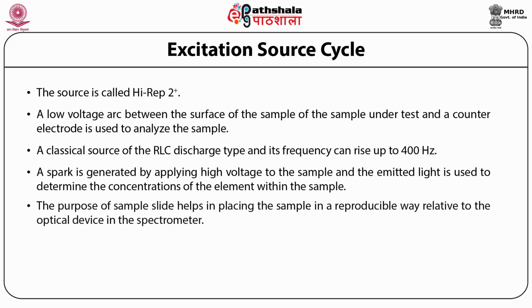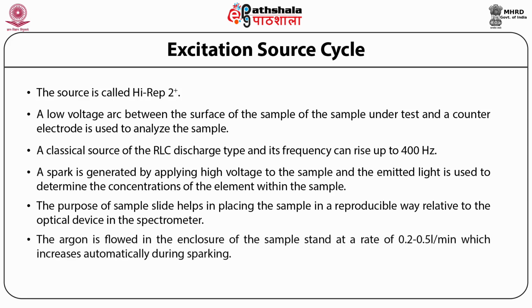The sample slide helps in placing the sample in a reproducible way relative to the optical device in the spectrometer. The argon is flowed in the enclosure of the sample stand at a rate of 0.2 to 0.5 liter per minute, which increases automatically during sparking. A water circuit is used to cool the table.